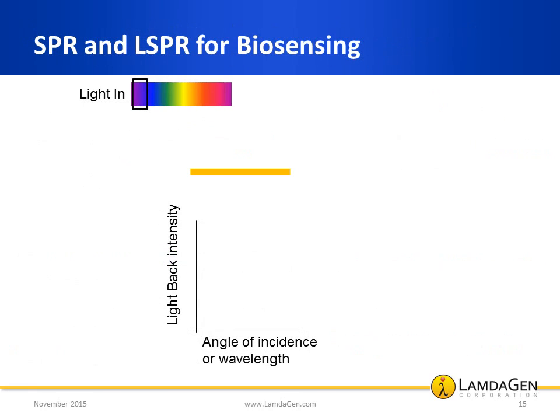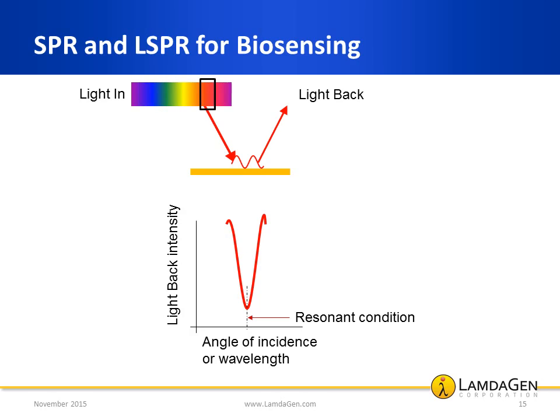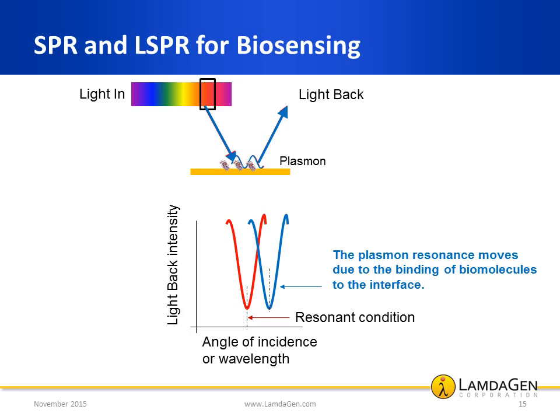Resonant conditions can be achieved by sending light onto the interface at a certain angle of incidence. If the resonant conditions are met, a surface plasmon is launched at the interface and results in a sharp decay of the reflected light. This can be accomplished by scanning the angle of incidence of light at a fixed wavelength or by using a broad light source with multiple wavelengths. In fact, the resonant conditions in both SPR and LSPR are very sensitive to the nature of the interface. If a thin layer of biomolecules is adsorbed onto the interface, the resonant conditions change. Even though the change may be very slight, it is measurable.